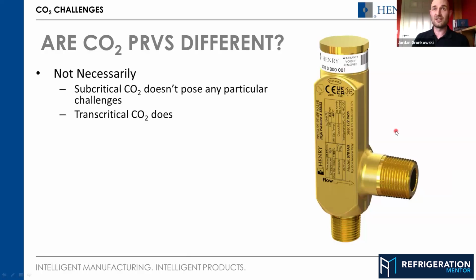Are CO2 PRVs different? Is the question I've asked here. The answer is not necessarily. Subcritical CO2 doesn't really behave any massively different from any conventional refrigerant. So although we at Henry have a high pressure range of valves specifically designed for CO2, all of our valves, even our low pressure ones, are suitable for CO2 because at your subcritical side, low pressure end, normal valves can work fine. But transcritical has its unique challenges.